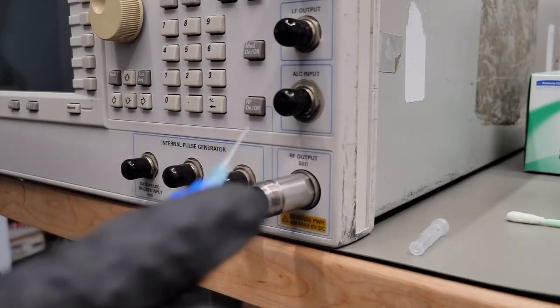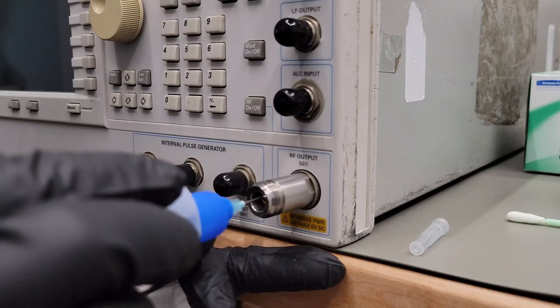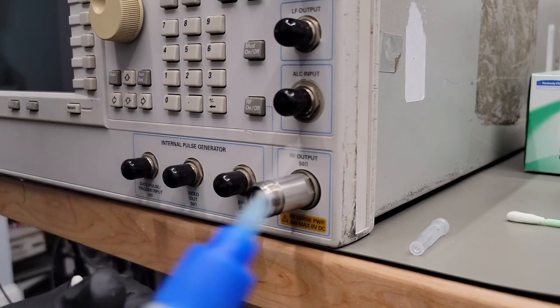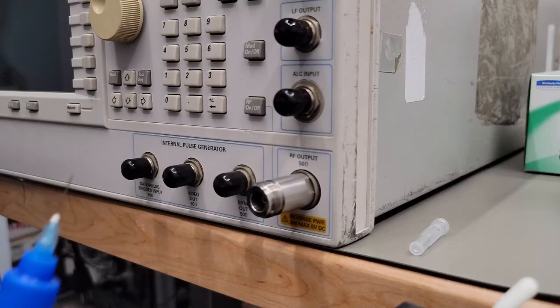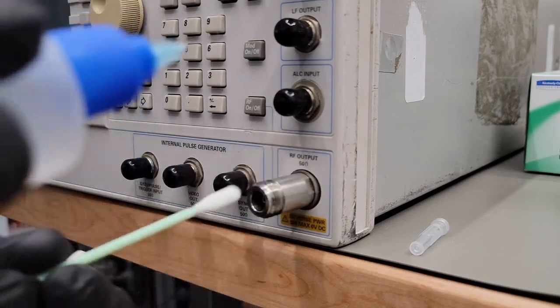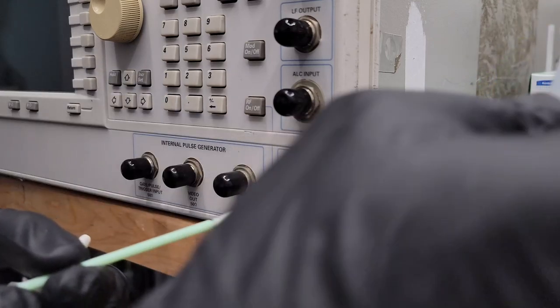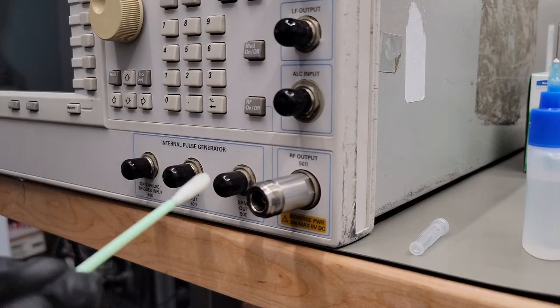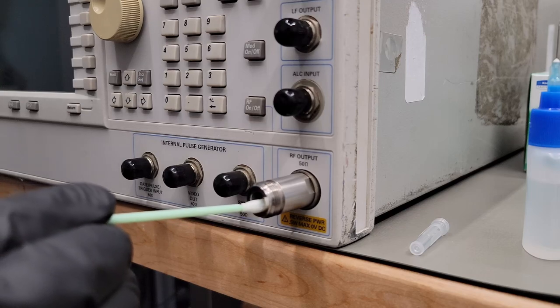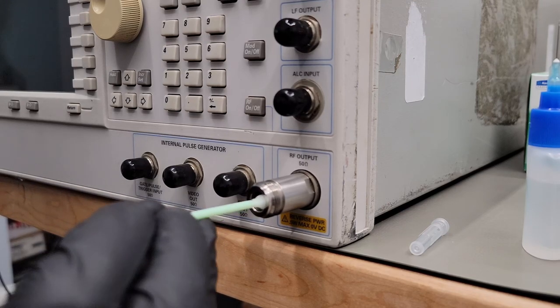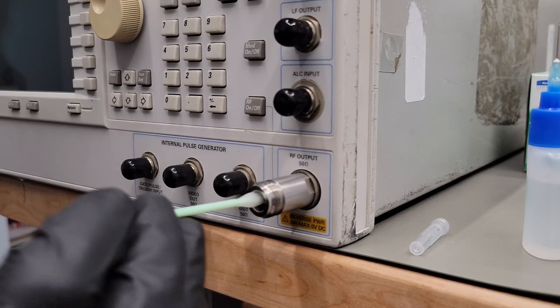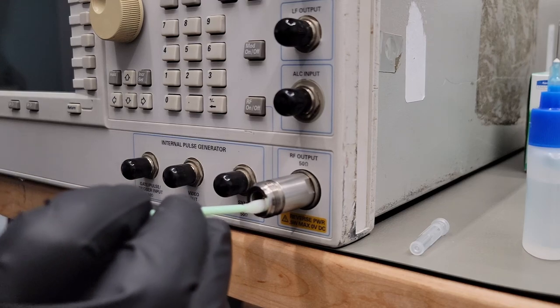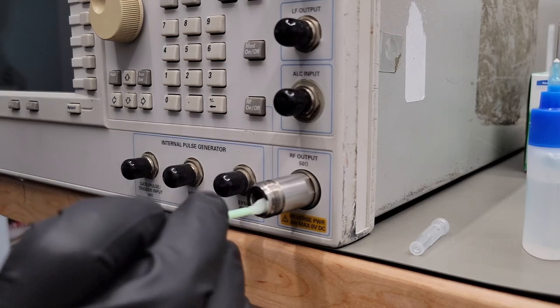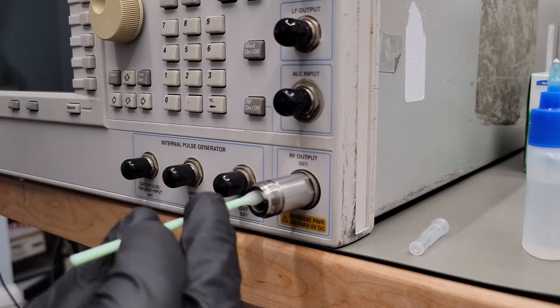And now to get deeper inside of this connector, that's when I use the swab. So you use a nice rectangular swab and apply some alcohol to the swab too. You just go ahead and carefully work your way around the center conductor. So you're cleaning the outside of the center conductor and the inside of the outer conductor.